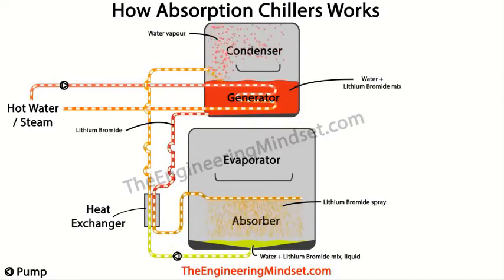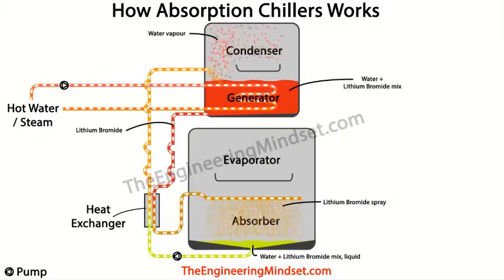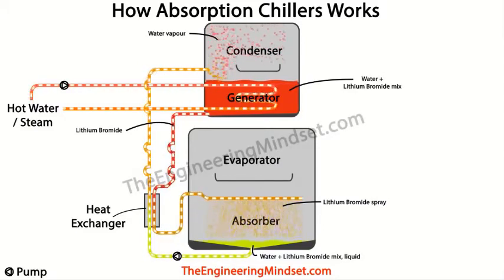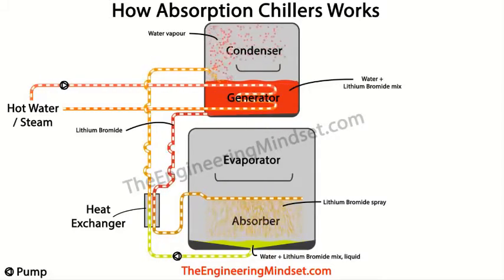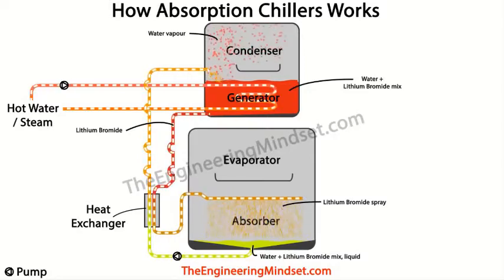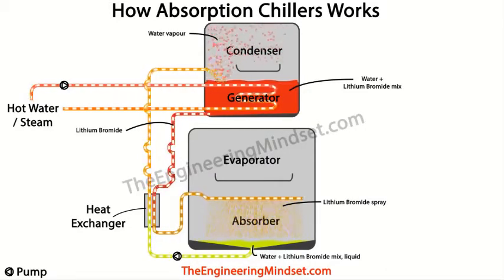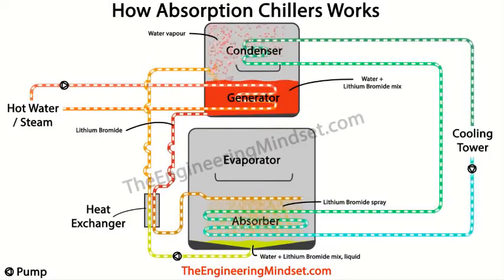This hot liquid flows down to the heat exchanger where it transfers its heat into the weak solution line, running in counterflow. Once the concentrated lithium bromide liquid has cooled down, it makes its way to the absorber where it is sprayed onto the chamber and will mix with the water before again being pumped to the generator to repeat the loop. But we will look at this part in more detail in just a minute.